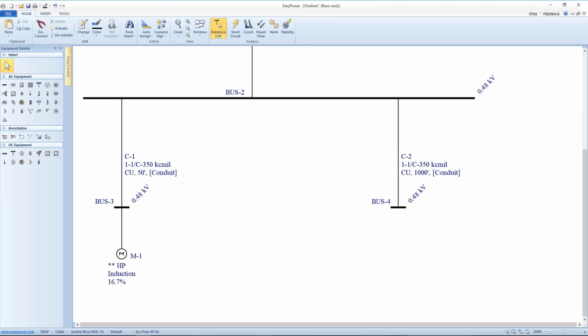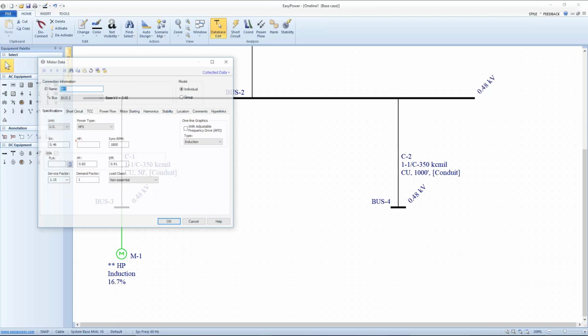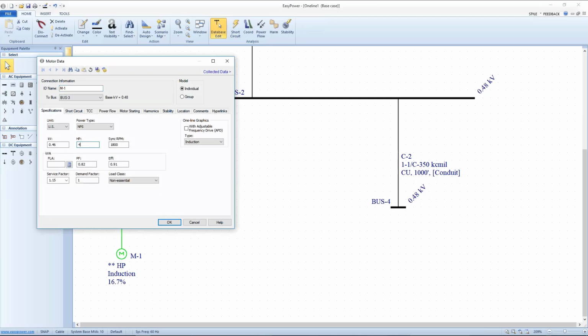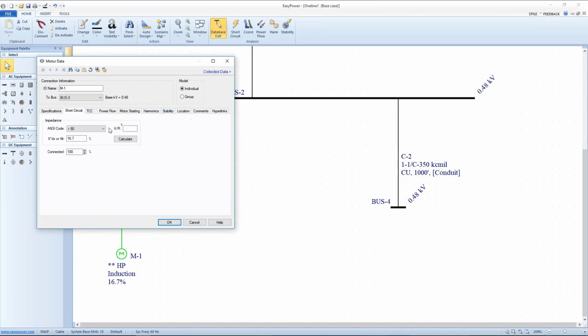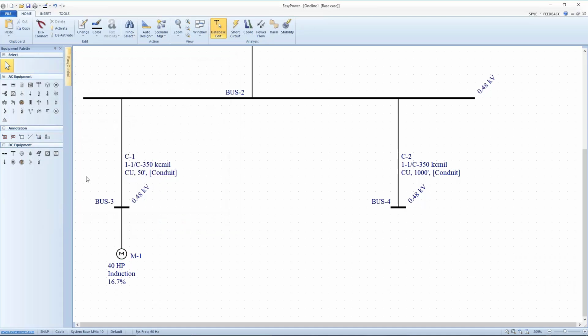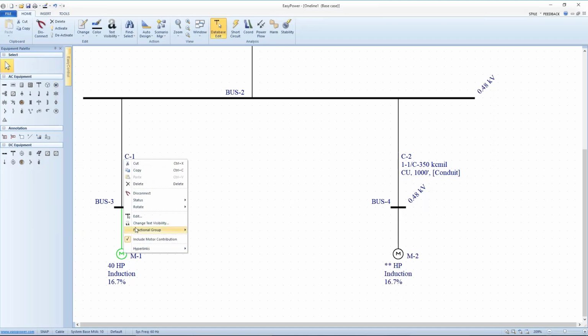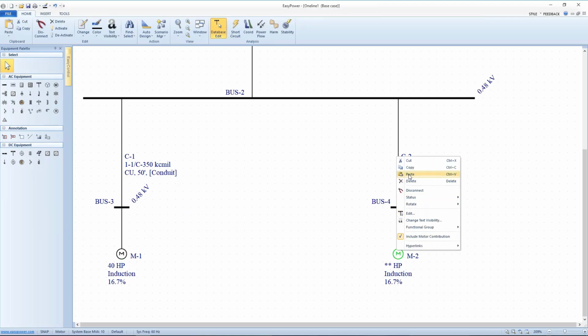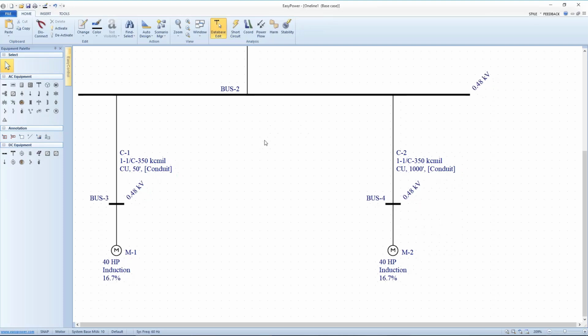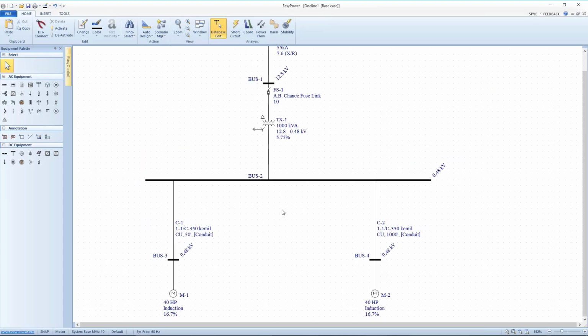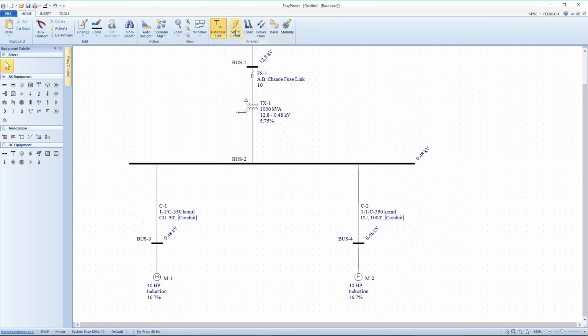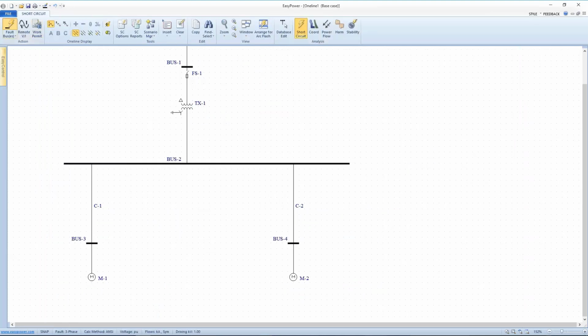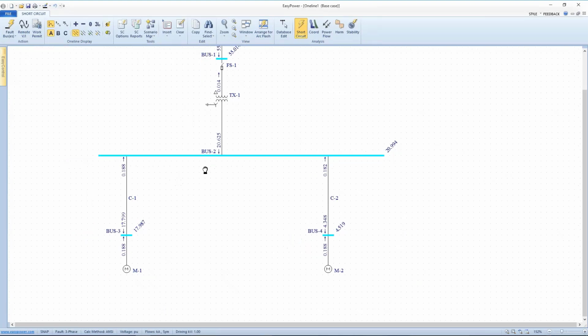So I'm going to put a motor down here, which is the end of this cable, and each of these motors was 40 horsepower. So we're going to take the typical values, calculate the X over R. And so we didn't have the specific numbers on these motors, but we're taking the average values. I'm going to copy, paste the same numbers over here. Now the reason I'm doing that is that IEEE and NFPA 70E recommend, as we do our short circuit examination, we look at contribution from both the system with and without motor contribution.